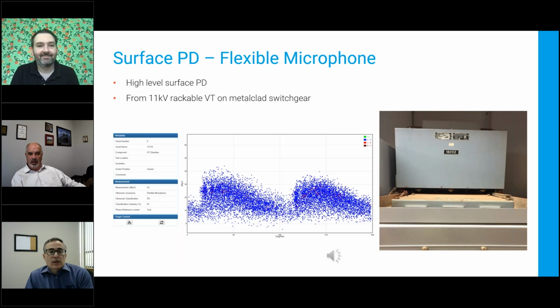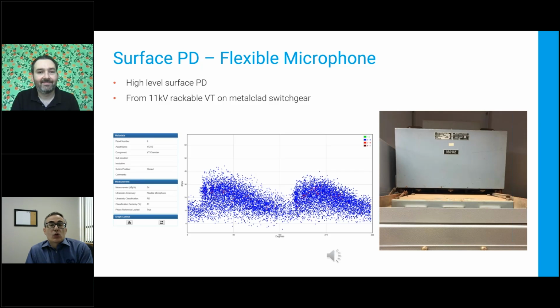For ultrasonics or acoustic sensing, this is what we would use for surface PD, and it could also detect corona. And so here's an example, a switchgear type of example. There's data that can be collected. I'm not going to get into interpreting the graph that's there, but you can have a sound clip, so you'll see folks wearing headsets when they're doing acoustic inspections. They're listening for a crackling sound similar to a frying pan sound. And there's data that can be collected and plotted for that.